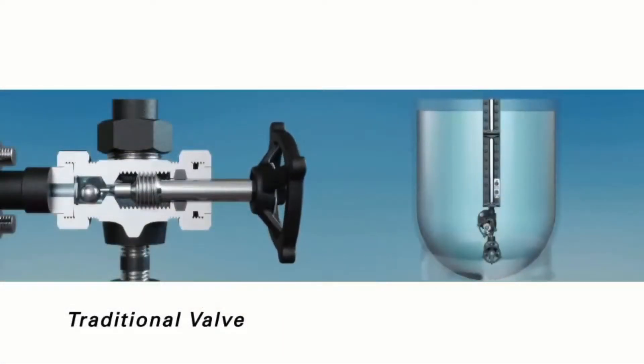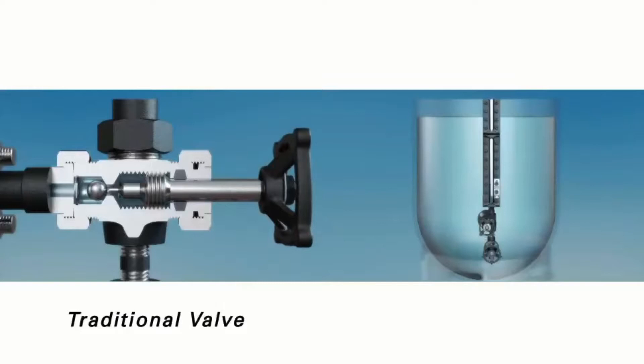When using a traditional ball check valve and commissioning a gauge assembly when there is already liquid present in the vessel, it is common for the user to open the valve too quickly, causing the ball check to engage and the level gauge to display a false level reading.